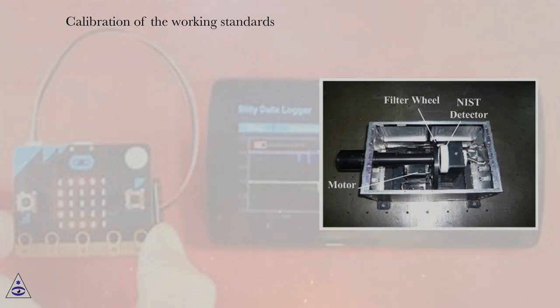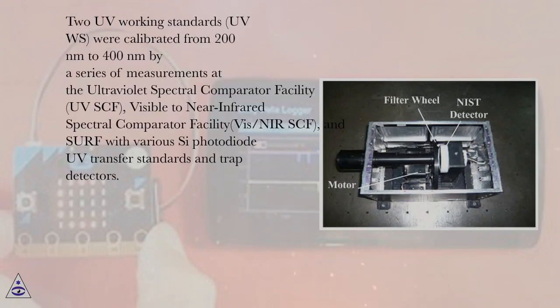Calibration of the Working Standards: Two UV working standards (UVWS) were calibrated from 200 nm to 400 nm by a series of measurements at the Ultraviolet Spectral Comparator Facility (UVSCF), the Visible to Near-Infrared Spectral Comparator Facility (VIS-NIRSCF), and various Si photodiode UV transfer standards and trap detectors.